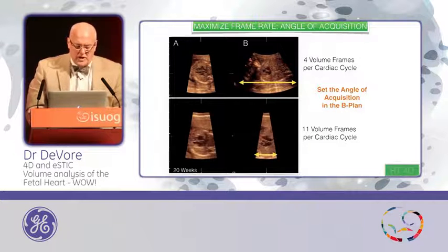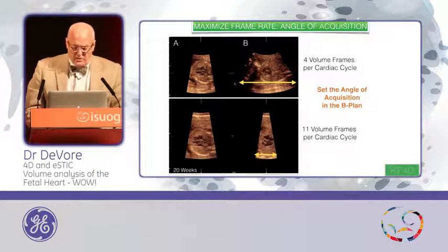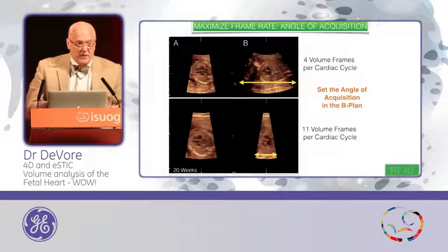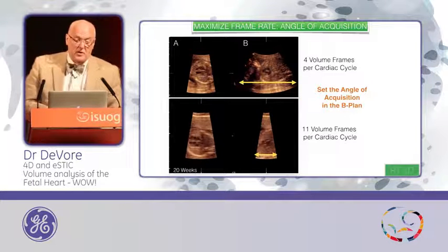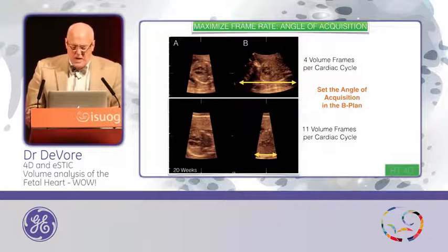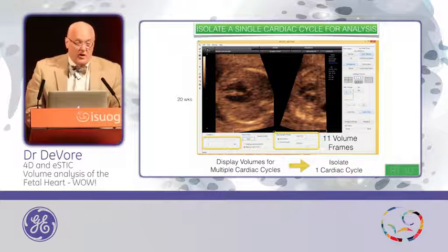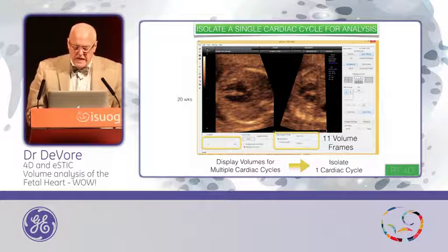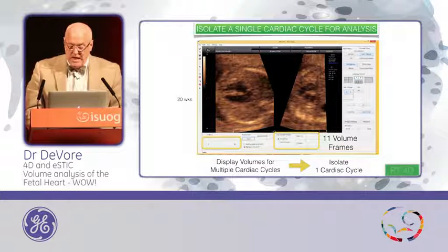If we look at how we improve the frame rate — that's the key element — a large B-angle sweep from the head down through the lower pelvis gives us only 4 volume frames per cardiac cycle, which is too slow for analysis. By narrowing the B window, we can go up to 11 volume frames per cardiac cycle and even higher, depending on the depth of the image and the adipose tissue of the patient. Half of our patients have BMIs over 30, so that presents a problem. Once done, here's a list of all volumes acquired in a two-second sweep, and we can identify the complete single cardiac frame or cycle for analysis.